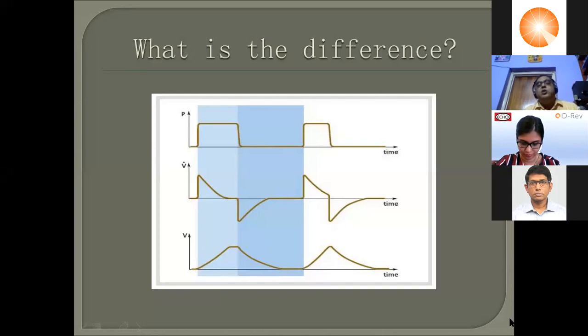So suppose you have set your flow termination criteria as 80%. For a supported breath, what happens? This is my peak flow right at the beginning of the inspiration. So this is my 100%. As my inspiration goes on, it goes down, down, down. When it drops by 80%, or reaches 20% of the original, then if you set it at 80%, the ventilator will cycle to expiration. If your flow termination criteria is 60%, then it will go down up to this level maybe, where it is 60%, and my expiration will start.